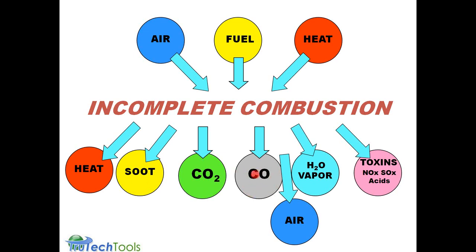That's the ultra toxic gas that's produced if you have incomplete combustion. You also have toxins that are entrained in the air coming into the system that can also be produced by the combustion process, like nitric oxide or sulfur dioxide. And these, in combination with water vapor when they condense, produce acids. That's why you sometimes see rusting or staining on combustion appliances, because the mixture of these toxic gases and water vapor creates literally liquid acids.